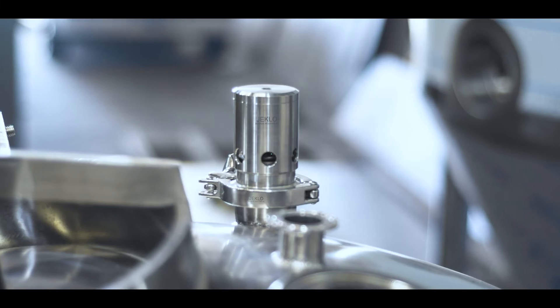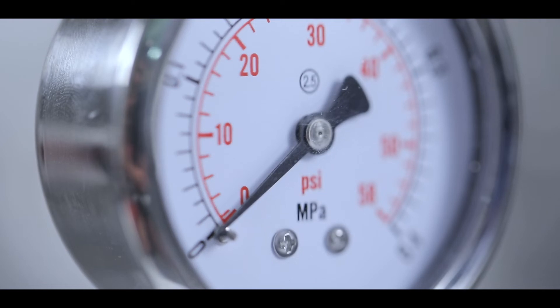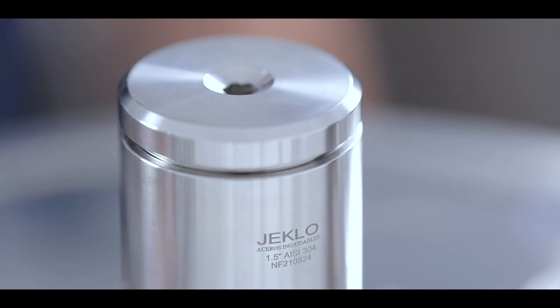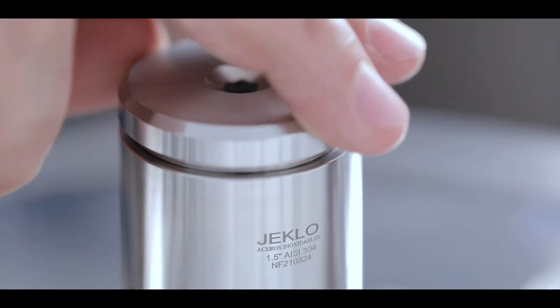For our relief valves, the opening pressure is adjustable between 0.5 and 2.5 bar. To regulate it, the upper cover of the valve must be unscrewed.